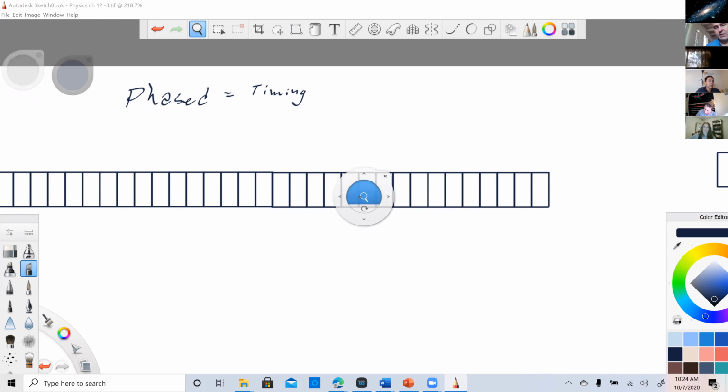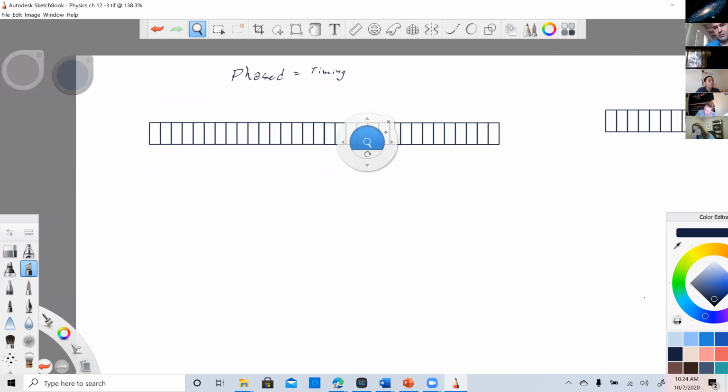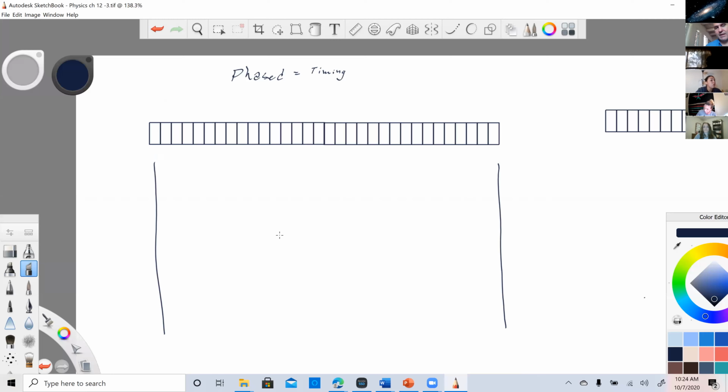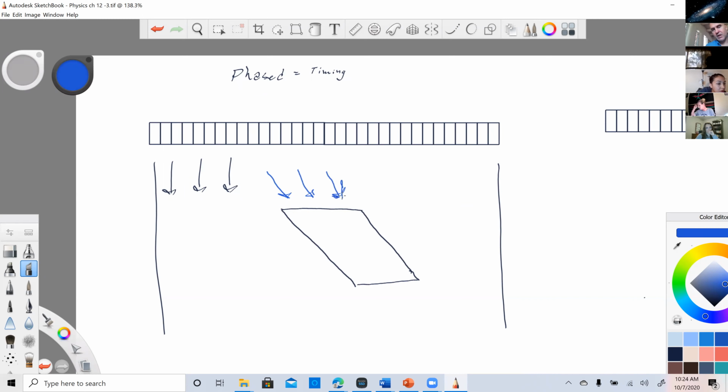When we do a grayscale image with our linear, by the way, guys, we are creating the grayscale image, which is square. And then we may overlay a color box, which is steered. So for the square, everything is straight down. For the grayscale, everything is straight down. And then after that entire picture is made, remember, this happens many, many times a second. Then, for the color box, the beam is angled. It's steered one direction or another. Then we go back to the gray, and then we go with the color, gray, color.